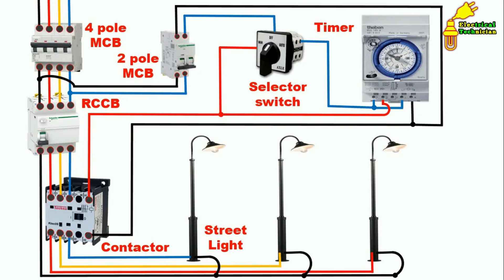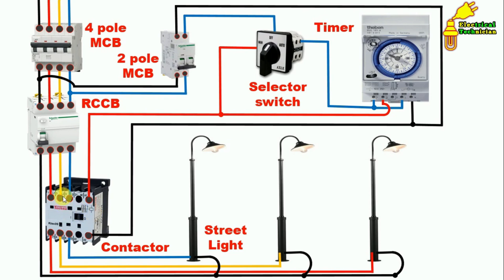Power wiring and control wiring are now completed. To turn on the street lights, first turn on the four-pole MCB and the RCCB so power supply reaches the contactor. We have two options: select manual position on the selector switch, and power supply goes directly to turn on the contactor; or select auto position, and when the timer operates as per the time set, the NO contact changes to NC, power supply flows to the contactor, the contactor turns on, power terminals get connected, and the street lights turn on.